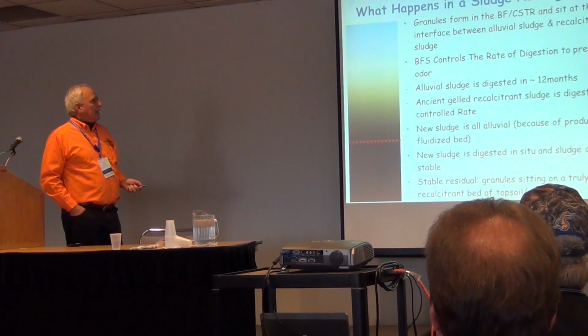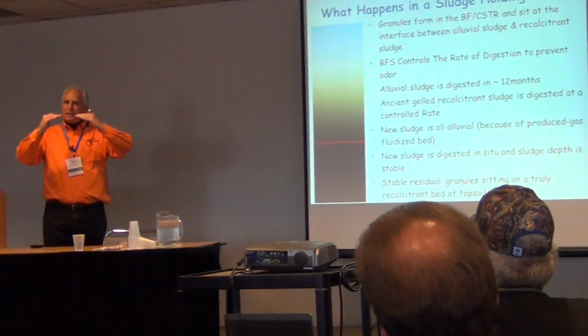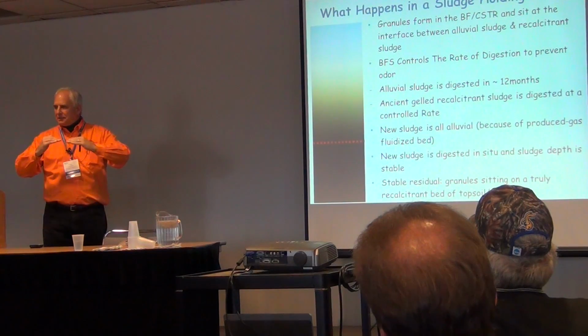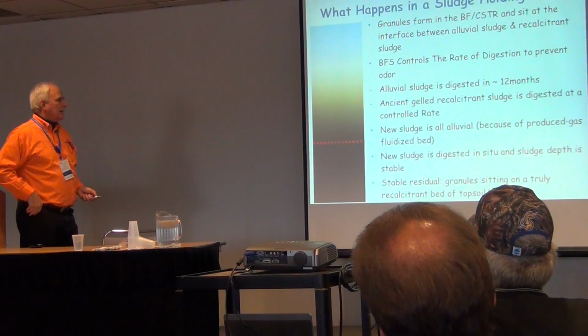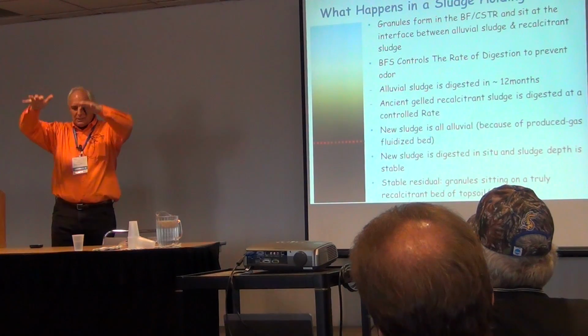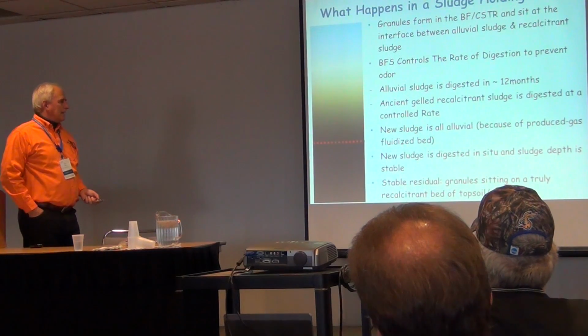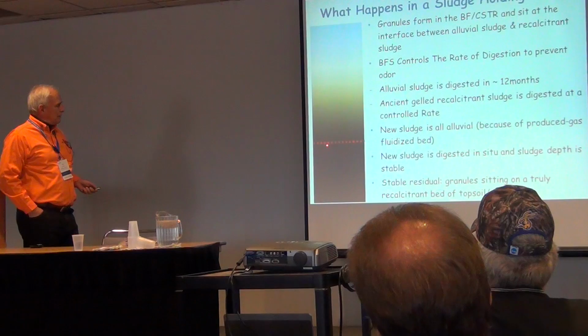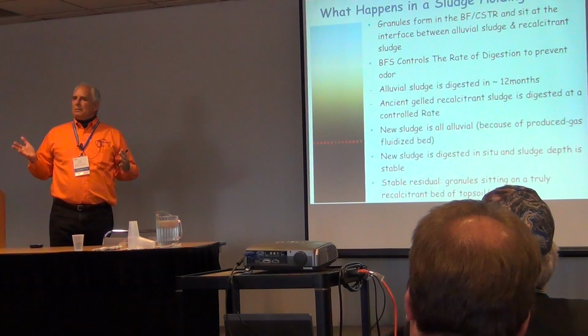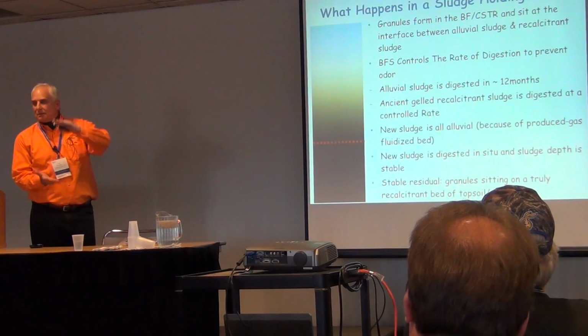I'll show you some data. And the ancient sludge is digested at a controlled rate. All you want to do is to digest it one skosh more than it's coming in, so it's always going down. So it doesn't matter if it takes a bunch of years, because as long as it's going down, you're winning. And any new sludge is all alluvial. Why? Because the methane is rising, and the new sludge is falling, and so that fluidizes it. So it gets digested. It never becomes recalcitrant gel. And then you have a stable residual, and this line will then come down around here. And what we find is that about 18 inches is the equilibrium depth. A little bit of that is recalcitrant sludge, truly recalcitrant, and the rest is the fluidized bed.